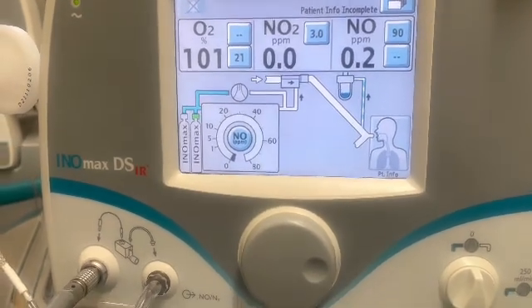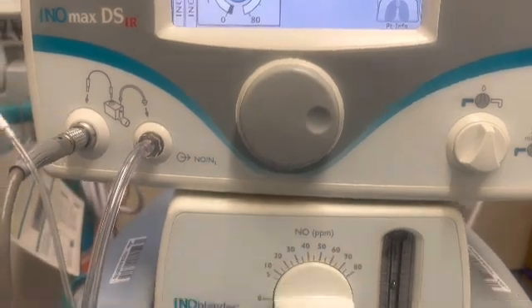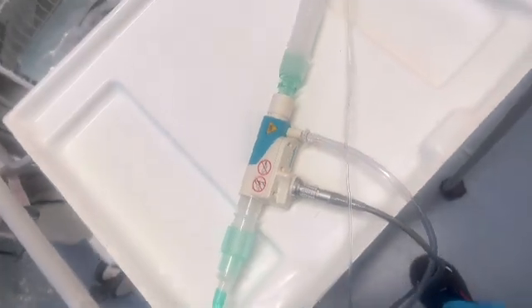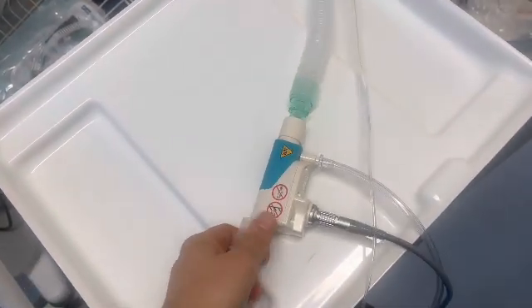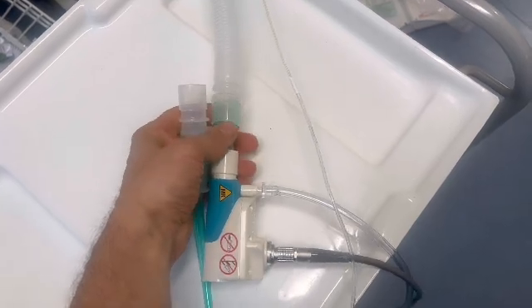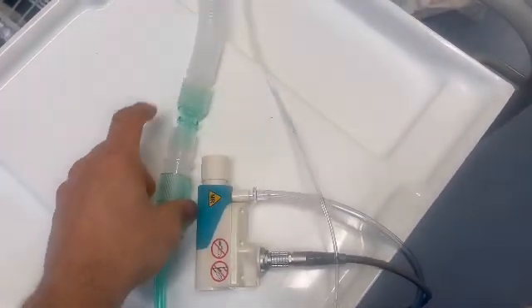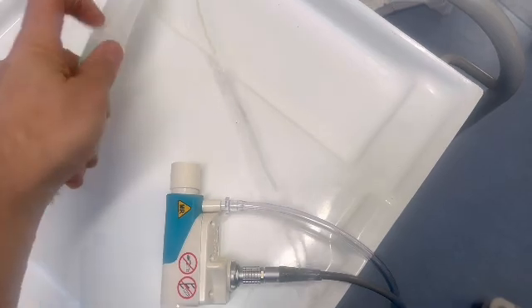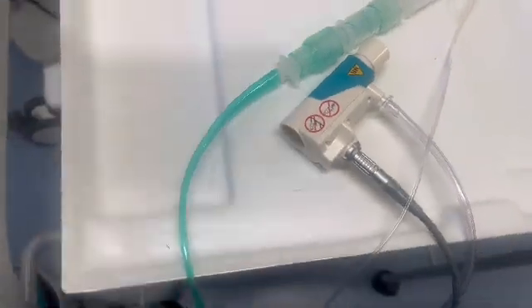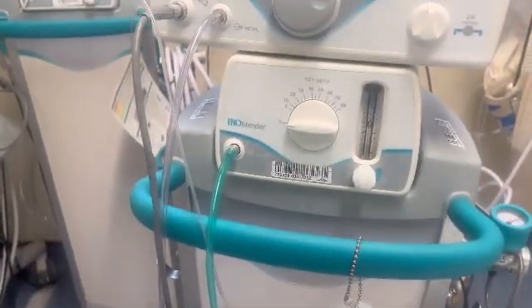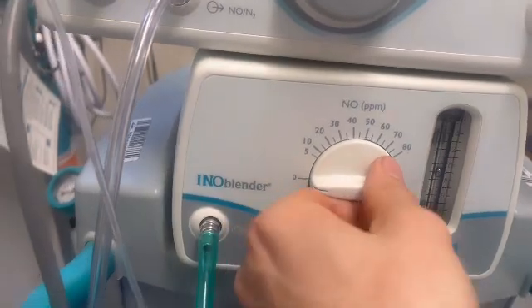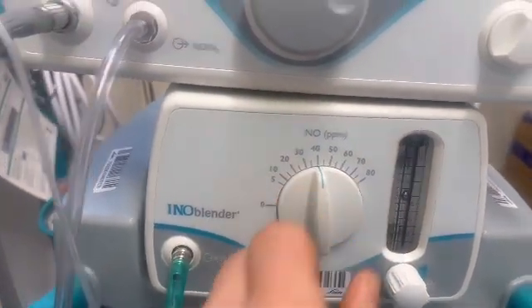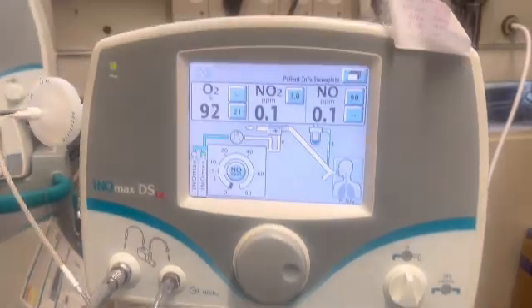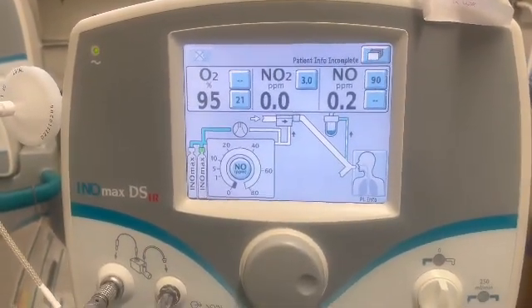The INO Blender works independently of the main unit to deliver a pneumatic supply of nitric oxide. Unlike with normal operation or using the backup switch, the nitric is not delivered to the injector module but through the oxygen port, so the injector module should be disconnected from the test circuit, with the test circuit attached to itself again. When this is done, the dial of the INO Blender should be set to 40 parts per million, with the O2 flow still on 10 litres.